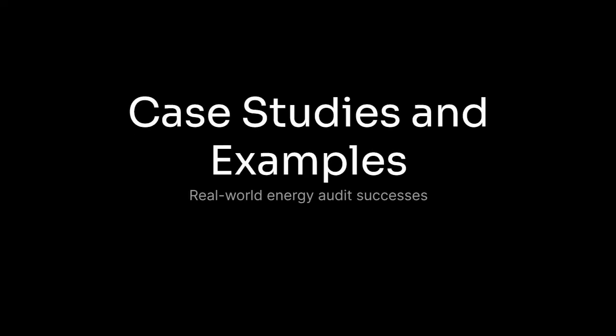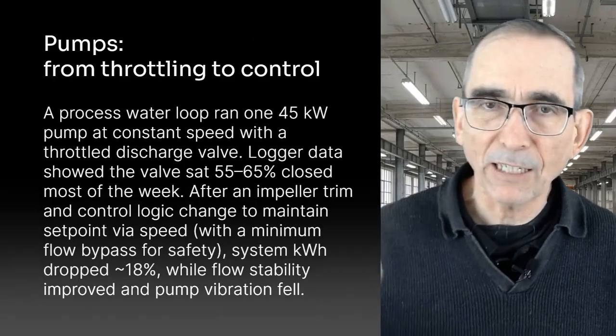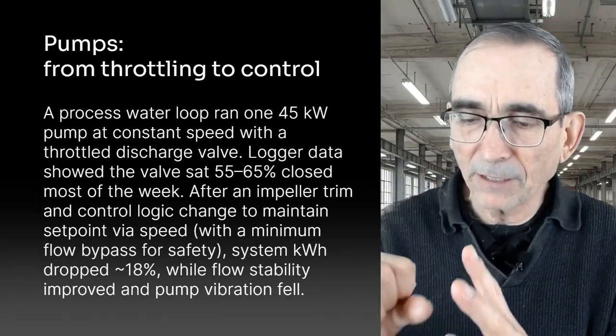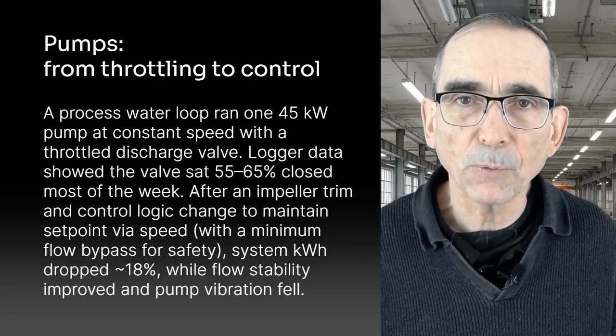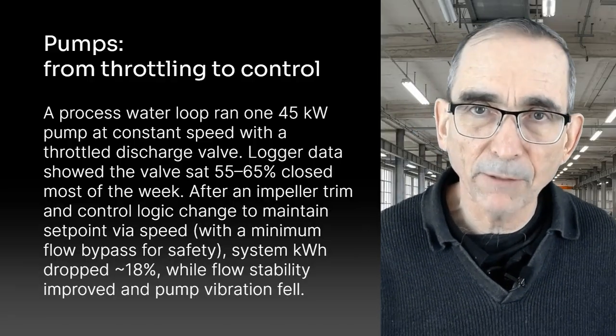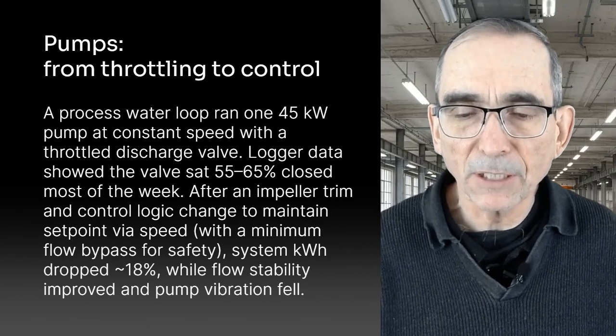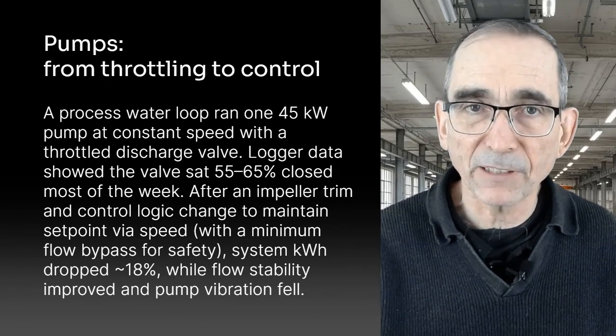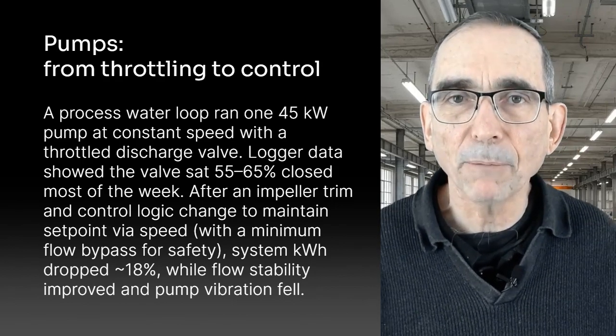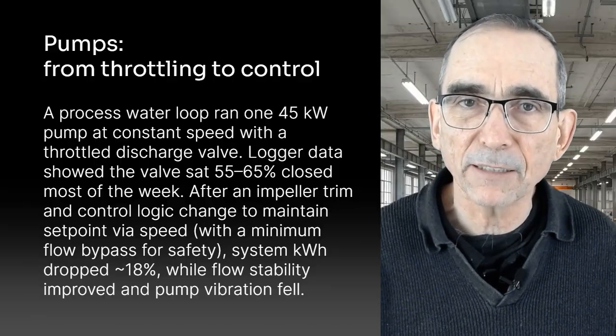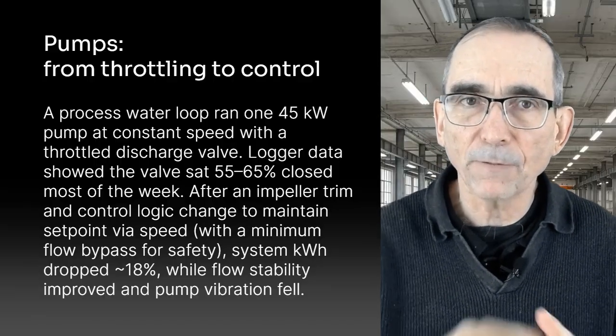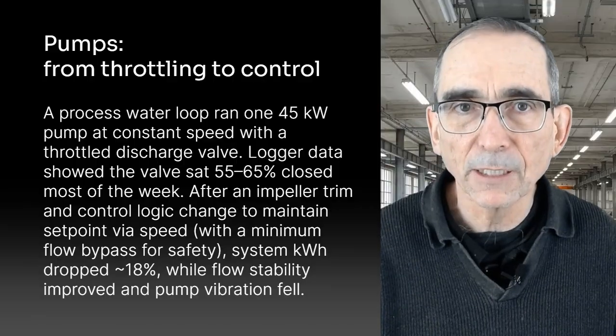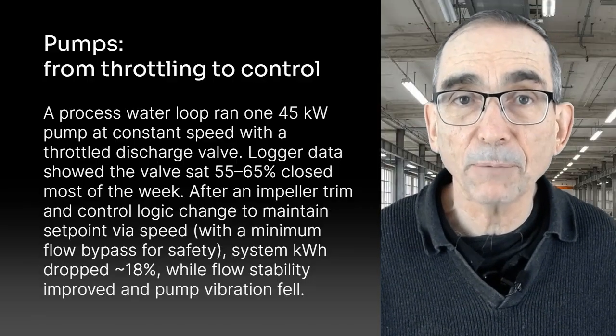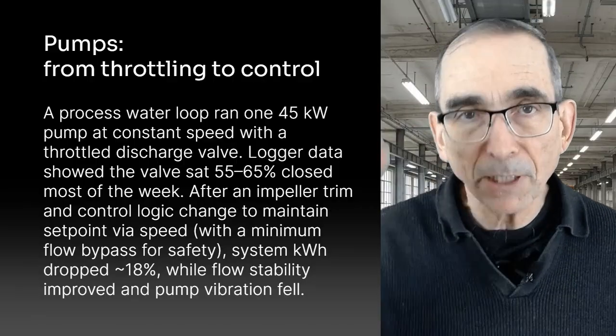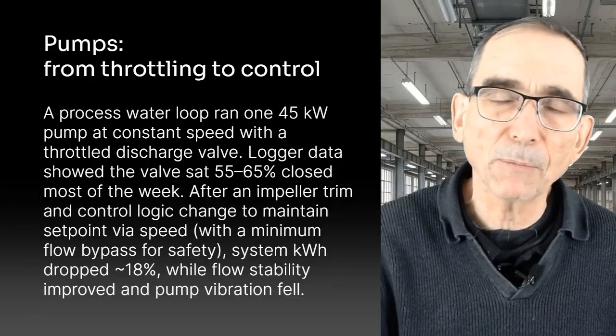So let's just give you some mini case examples. Here's an example: a pump which was heavily throttled. That means a valve reducing the flow rate of water. There was a process water loop that ran a 45 kilowatt pump at a constant speed with a throttle discharge valve, and logger data from the SCADA system showed the valve set at 55 to 65% closed. The fix was trimming the impeller on that pump and changing the control logic to maintain set point via speed, with a flow bypass for safety. There's a bit of capital cost involved, but system kilowatt hours dropped by 18%. Flow stability improved and pump vibration fell, extending pump life.